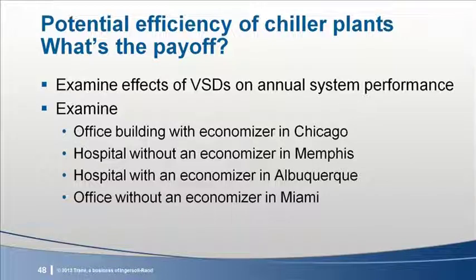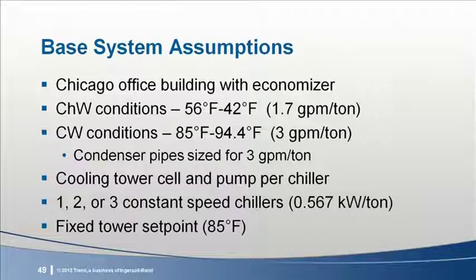Since in past E&Ls we've spent so much time on the chilled water side, we're going to concentrate on the condenser water side today. We'll examine building types in 4 locations. Shown here is our base system configuration for the office building in Chicago. The building has an airside economizer, so during many hours of building operation, the chilled water plant will be off.